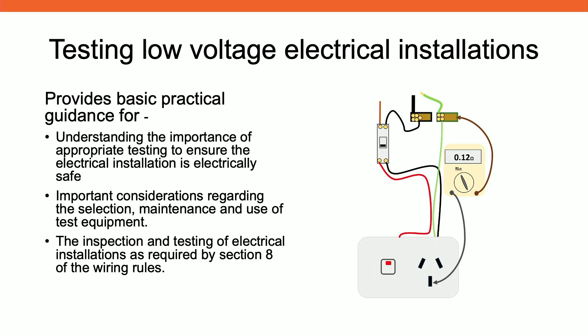So there's another book which is quite large in comparison. It covers testing of low voltage installations. Up the front, it gives you an understanding of the importance of the appropriate testing to ensure an electrical installation is electrically safe. And we keep in mind the two things that are most important. One is direct contact. We need to prevent anyone having direct contact with an energised electrical part. And the other is indirect electrical contact, which is when there's a fault and earthed appliances, class 1 appliances, the frame will become energised until the protection operates.